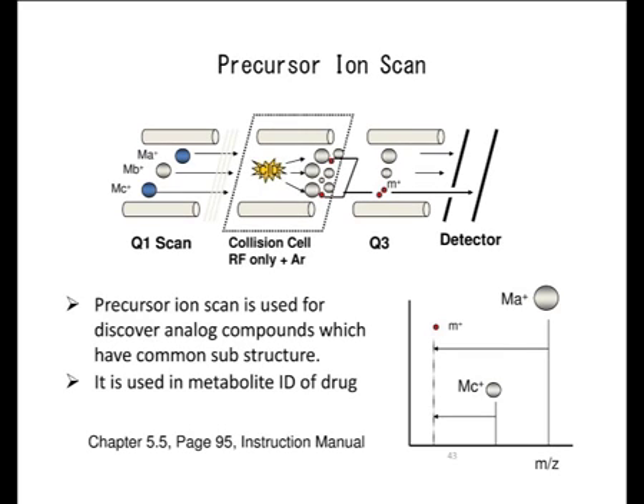Then the precursor ion scan. In the precursor ion scan, your Q1 is in the scan mode and Q3 is in the SIM mode, the opposite of the product ion scan. You look for a group of compounds that have a common functional group or common product ion. For such screening purposes, you use the precursor ion scan.